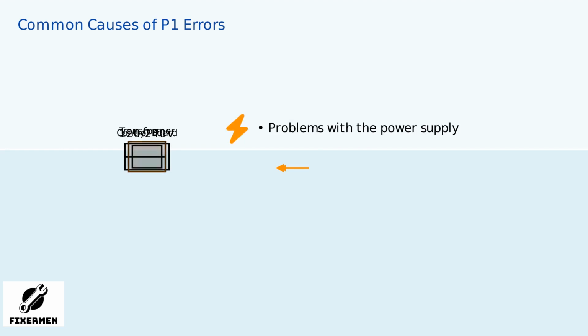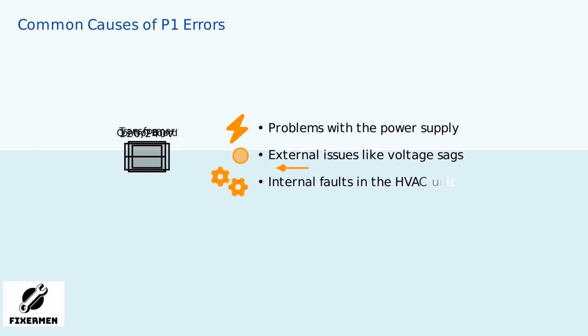Several factors can trigger a P1 error in Carrier HVAC systems. These include problems with the power supply, such as a faulty transformer or loose wiring. External issues like voltage sags from utility fluctuations or power grid overloads can also cause this error. Additionally, internal faults within the HVAC unit, such as a failing capacitor, blown fuse, or control board malfunction, are common triggers. Remember to check the breaker before assuming a major malfunction, as power outages and brownouts can also lead to P1 errors.